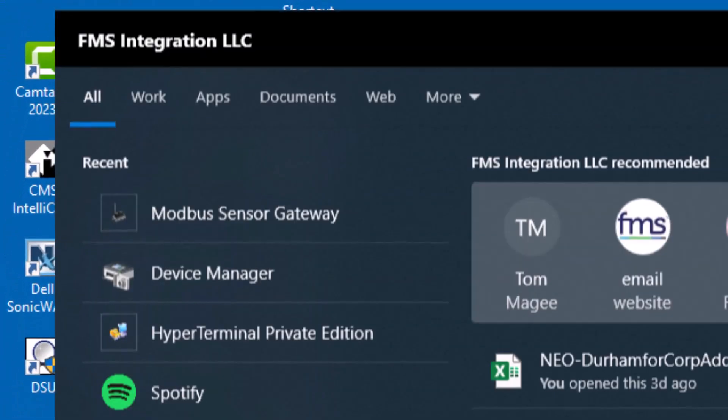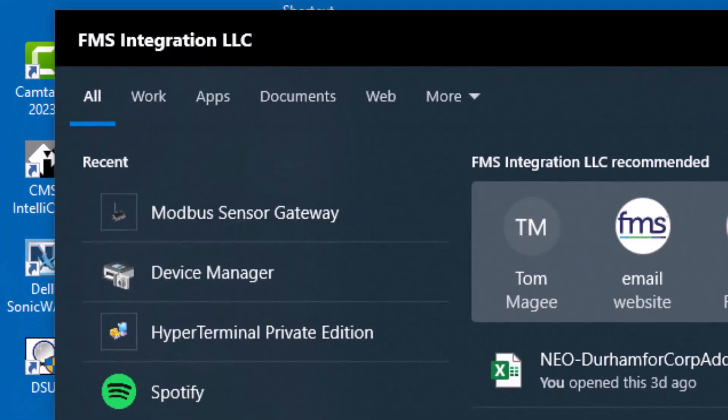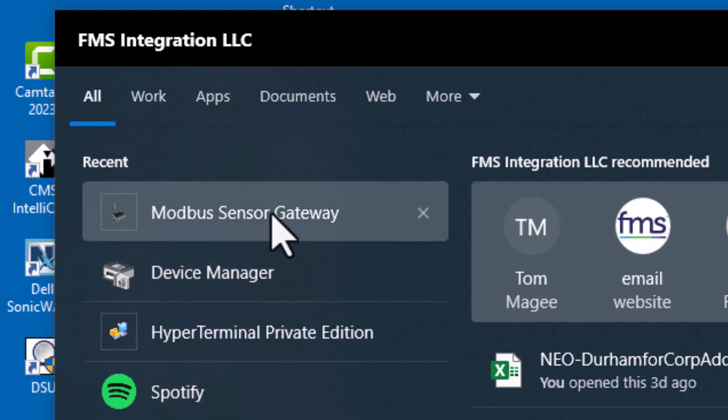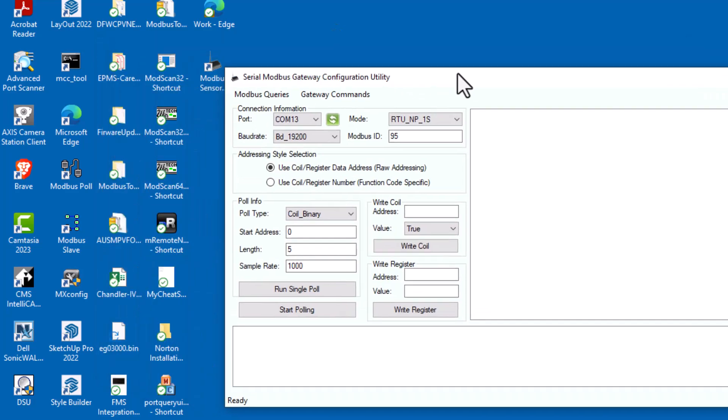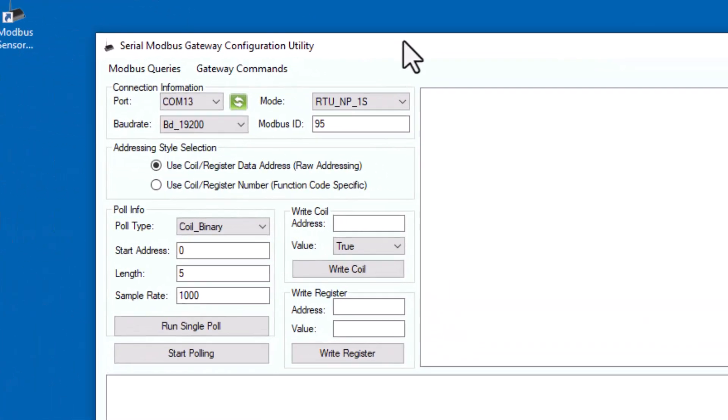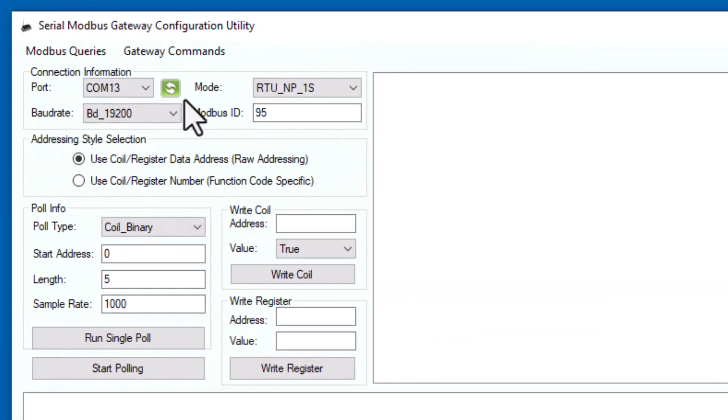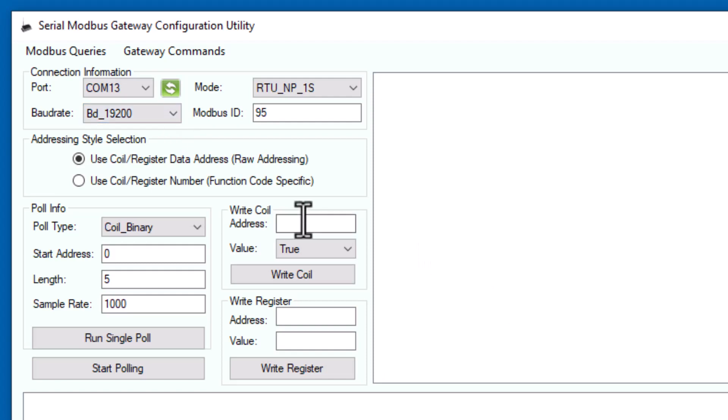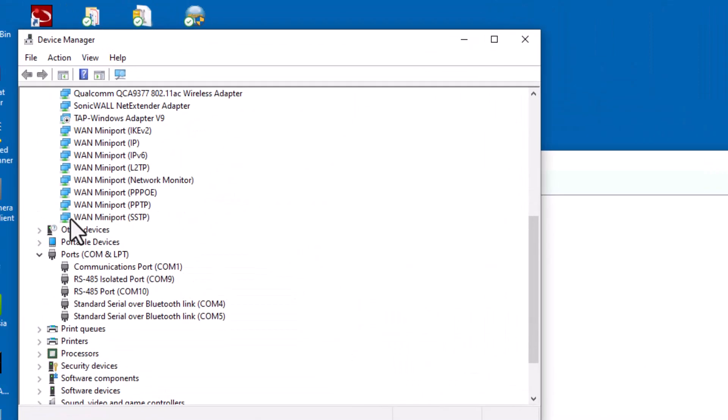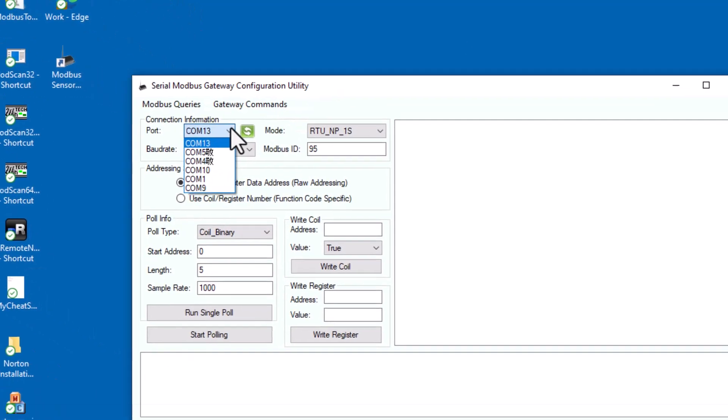Once you have your wiring set up and established, you can go to their website and they have a thing called the Modbus Sensor Gateway, their utility tool. You can open this up. You'll have to know what COM port is being designated by your machine for your USB to RS-485 connection. If you don't know what your COM port is, you go to your Device Manager.